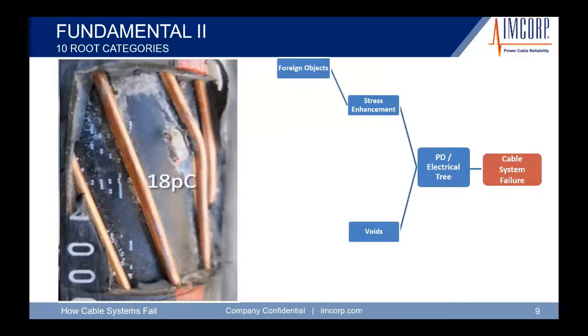Foreign objects. So this is a cable that was laid in the ground and then backfilled. A foreign object, a sharp rock, penetrated the jacket, went into the semicon, actually penetrated the insulation as well. We're able to find this. Now, again, with this type of foreign object, this cable could last 4 or 5 years, maybe even longer, depending on the load, depending on the voltage, but eventually it can fail.